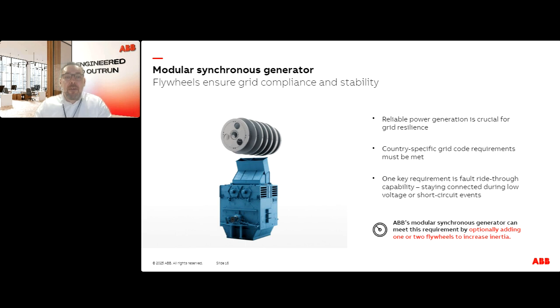So basically, one of the most demanding grid code requirements is to stay connected when there's a low voltage or short circuit event somewhere in the grid. This generally requires the gensets to provide high inertia and fast response to ensure that the plant stays in synchronism with the grid when the fault is clear and voltage returns to nominal. To ensure this, we have come up with this solution to have increased inertia within the generator, because that's one of the key ways to comply with these sometimes quite long fault ride-through requirements.